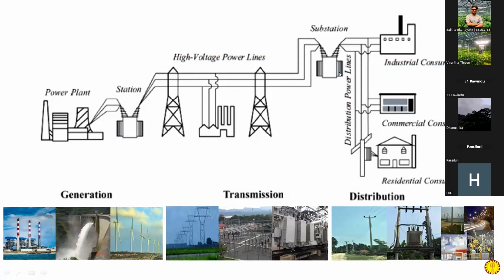Even 33 and 11 kV voltages have few customers directly using those voltages, since they have their own transformers. Domestic customers can't use 33 or 11 kV. So you might have seen another set of transformers by the road, or on top of poles, the small transformers. Those step down again from 33 kV to 400 volts. That 400 voltage is the three-phase voltage, so if you have a single-phase supply, you get 230 volts. That's what happens in the power system.